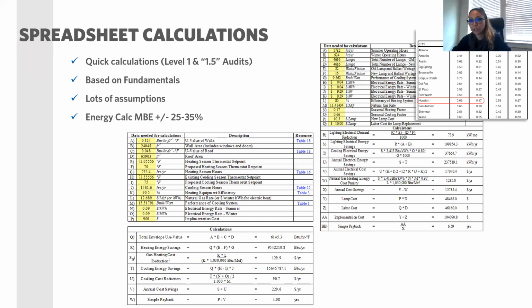So when it comes to the calculations, there are different ways. Pretty much the audit level determines which calculation methodology we will use. For level 1 and 1.5 audits, we try to use spreadsheet calculations, which are very quick, based on fundamentals like heat transfer basics, and require lots of assumptions. Like if we don't know the U value or the R value of the envelope, there are some pre-developed tables that we can use.